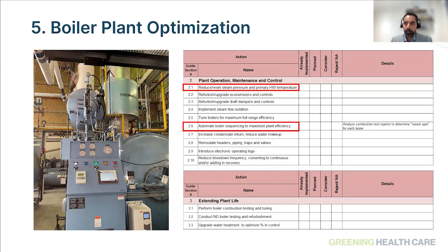Today we're just going to focus on the two easy ones that you can work out with your team, and we're going to have a separate webinar going into more detail on these individual measures. Ask the question: if you have a steam plant that's currently running at 110, 120, or 100 psi, you may ask your team what's the reason behind it, because sterilization generally needs around 65 psi dynamic steam pressure. So there might be an opportunity to reduce the overall steam pressure by test and trial, and you will see what the results look like. There's an opportunity to work with your team to optimize just by changing these set points.